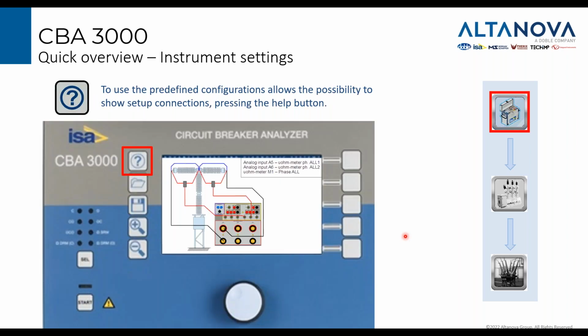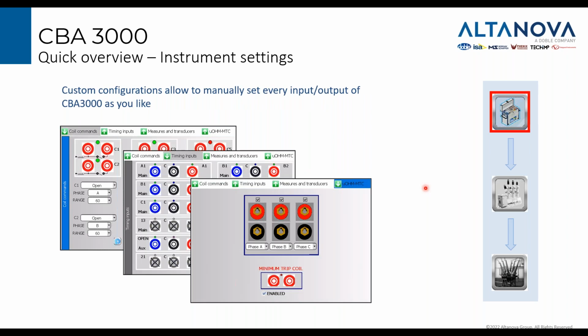Once you perform this setting, then on the screen you can see the suggested wiring, because on the front panel or on the panels in general, you don't have a clear, precise indication, because every input is programmable. So you need something telling you what must be connected and where. Everything is very clearly indicated by pressing the question mark button. There is also the possibility to make a manual configuration, but this is necessary only in very special cases.